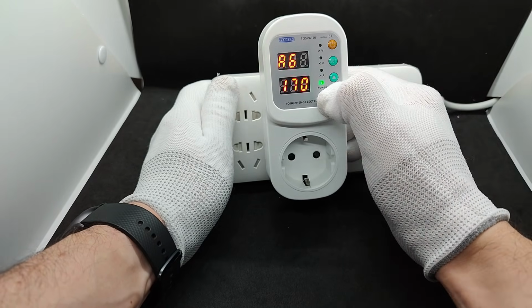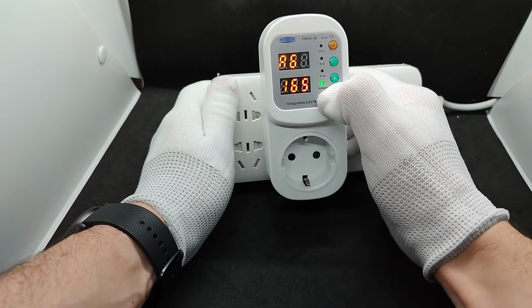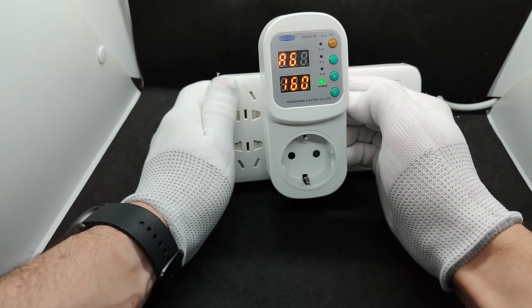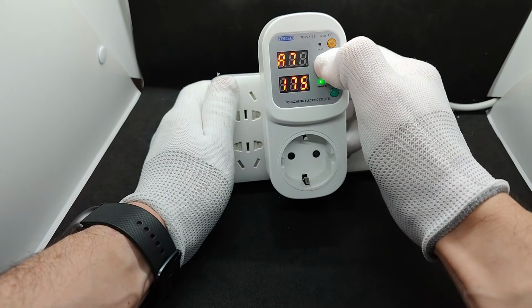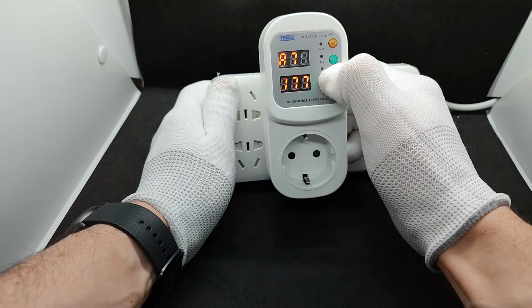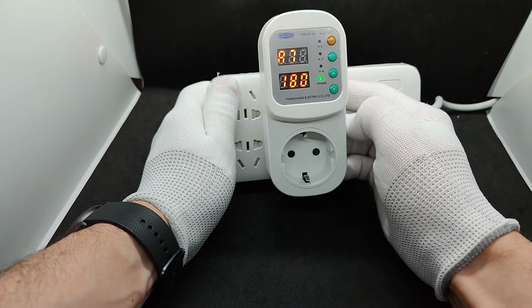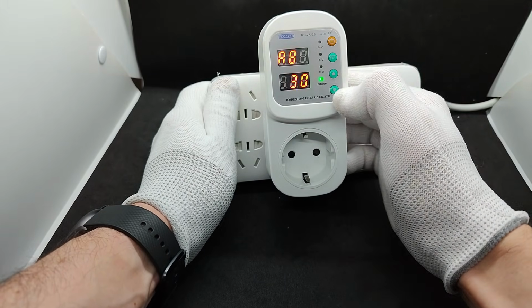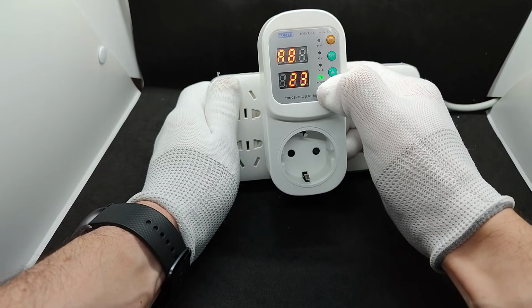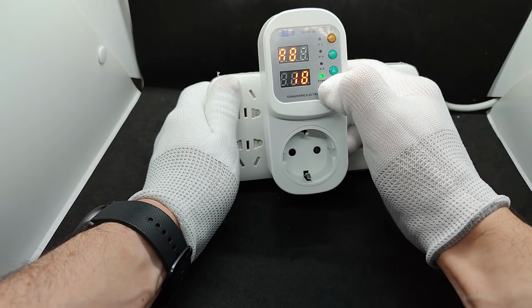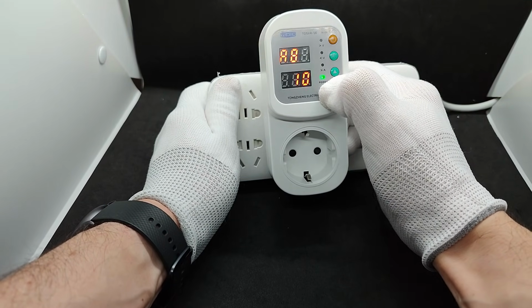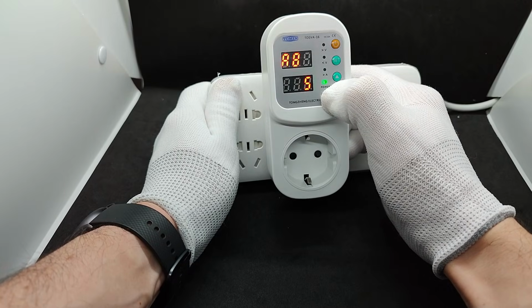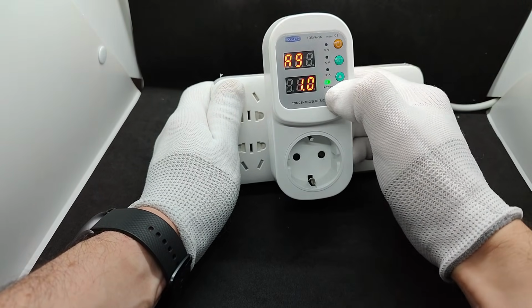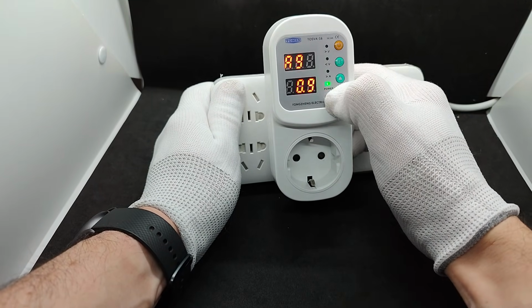Item A6 is the shutdown threshold, 170 volts. I set 160. Item A7 is the turn-on threshold, 175 volts. I set 180. A8 is the delay before turning on, 30 seconds. I set 5. The arrow button can be held for fast value changes. A9 is the delay before turning off, 1 second. I set 0.1.